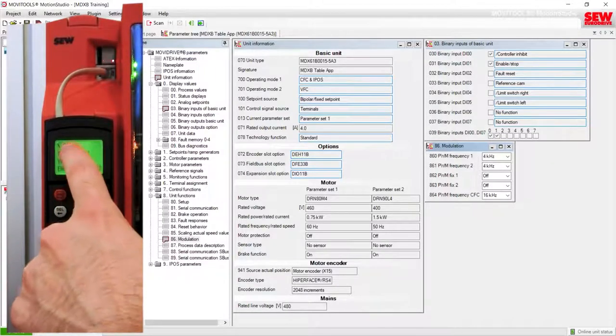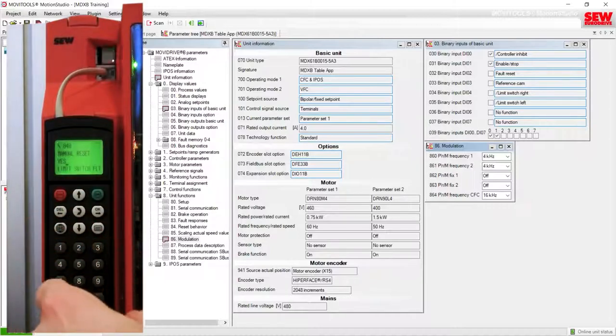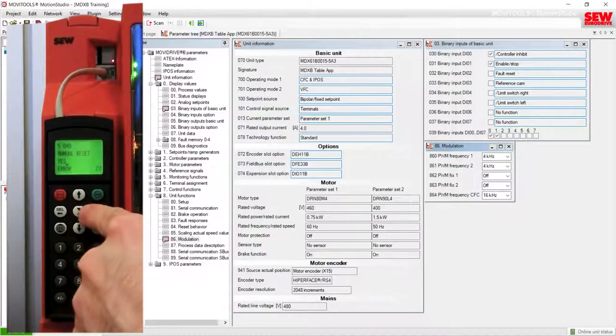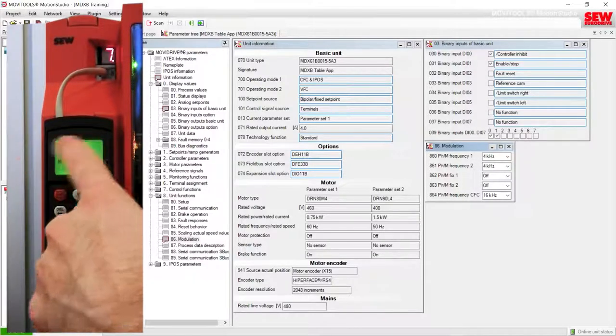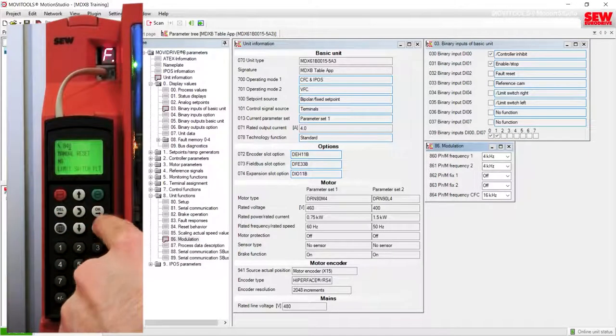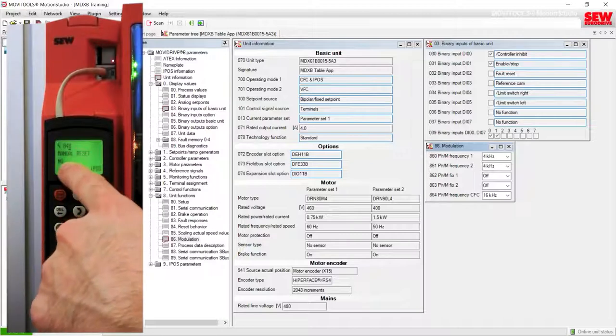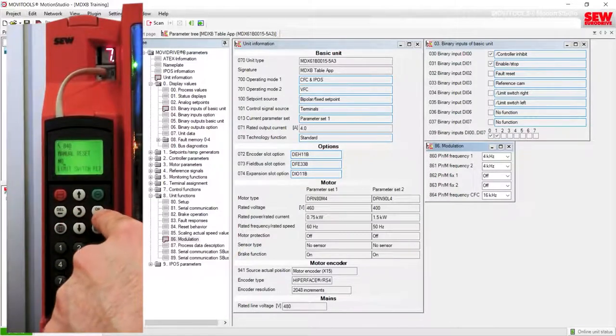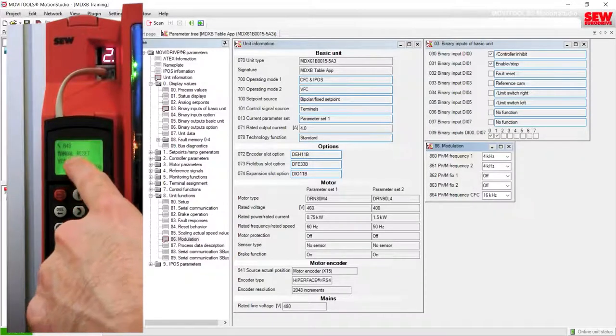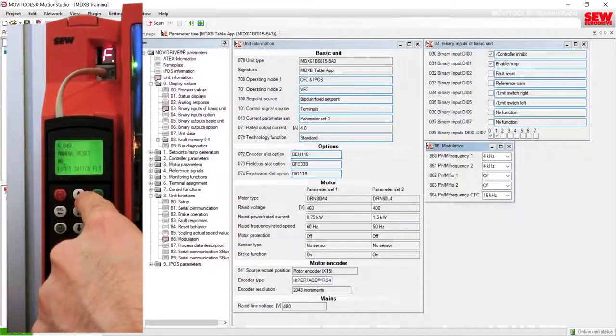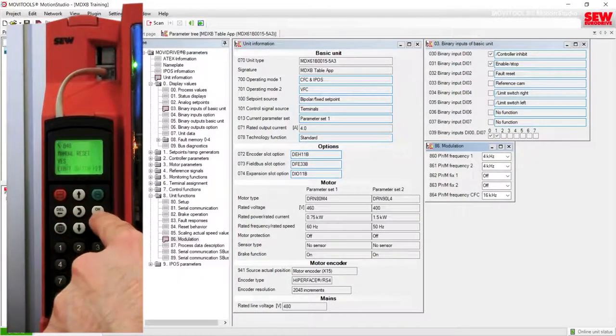To get out of the fault message screen, we press the delete key as shown at the top of the display. This automatically jumps us to parameter 840, which is the manual reset parameter for resetting the fault using the keypad. If we don't want to reset the fault, we can press the switch key to move the cursor from edit mode back up to the parameter number, and then navigate elsewhere or press the menu key to back out. To reset, we press the OK key to move the cursor into edit mode, use the up arrow to change the value from No to Yes, and then press OK to confirm.